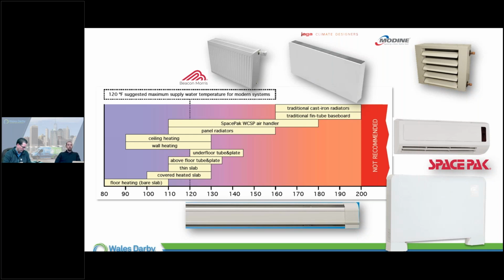If I can get the BTUs I need at 120 degrees where my heat pump's going to perform at the most efficient, then what's the problem? There's a couple other things we have to look at - we start to talk about COPs with heat pumps and where they're efficient, and maybe it doesn't make sense if those COPs aren't great enough to really show a savings.